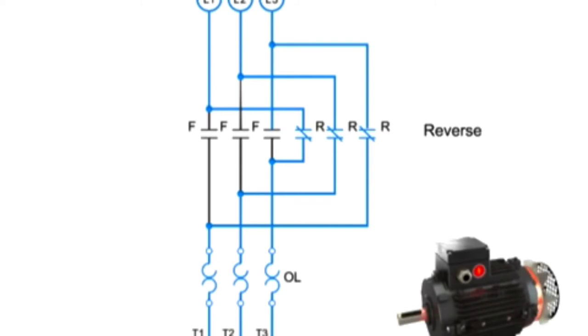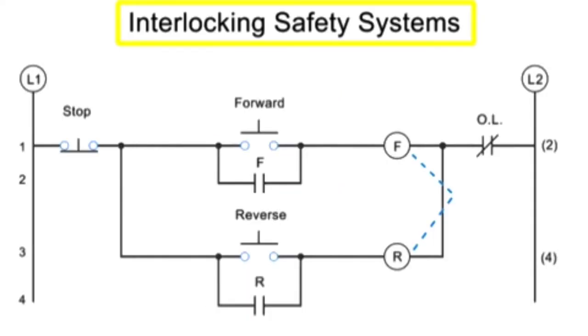In order to protect against this kind of short circuit, manufacturers employ three types of interlocking safety systems. Interlocks create a web of safety checks within a circuit to prevent both forward and reverse coils from being energized at the same time. They are represented in circuitry diagrams by a dotted line.